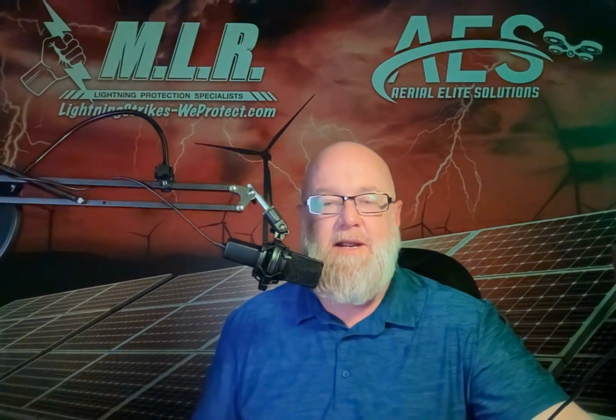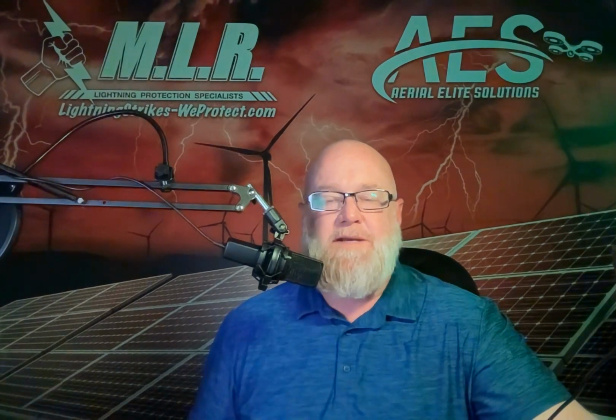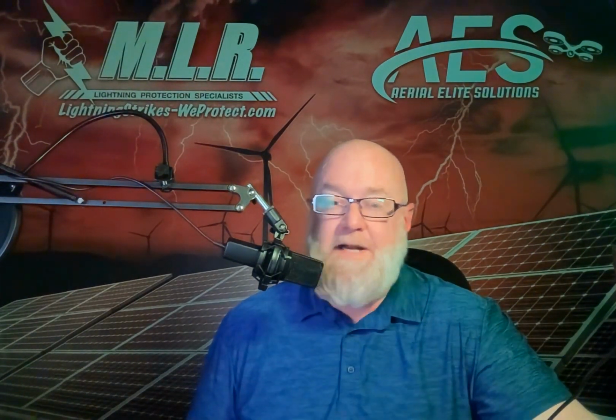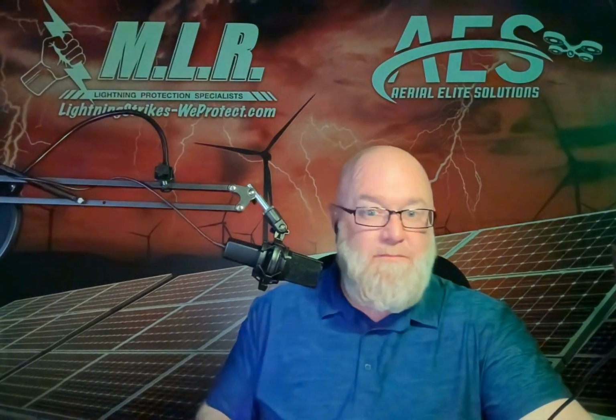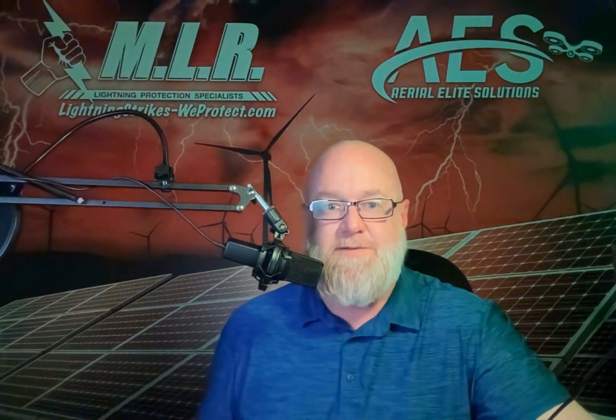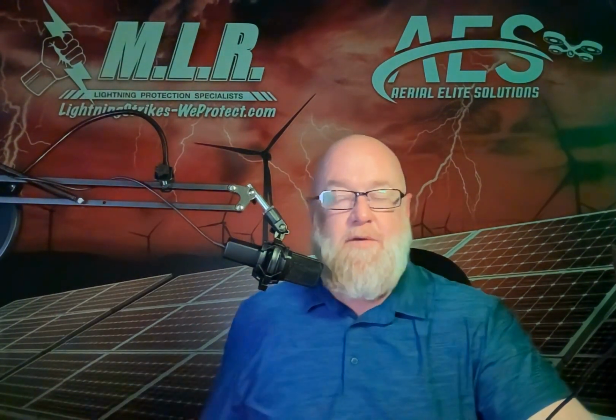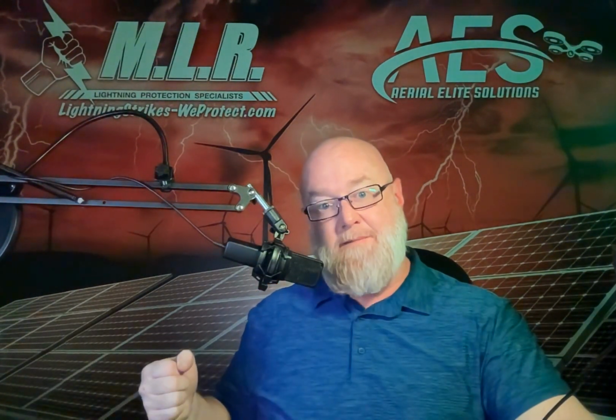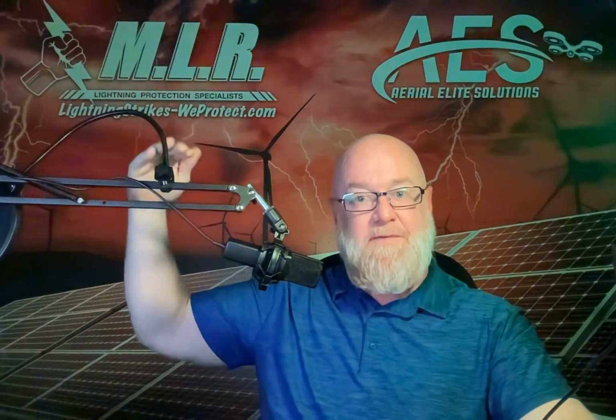Okay. So if something is in that rule with having to protect the extremities that are taller than 10 inches above our air terminals, that's regardless of what it's made out of. It doesn't matter if it's made out of plastic, paper, rock, paper, or scissors. It can be made out of anything. We got to put a lightning rod on it. If it happens to move, then we have to put a lightning rod right next to it that sticks up tall enough that it's 10 inches taller. So, there's that.